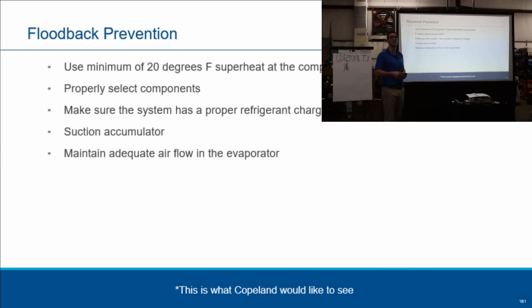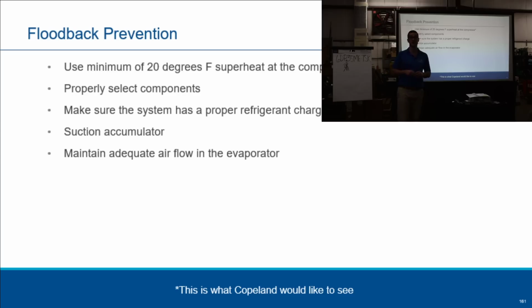It's no different than a supermarket application. I'll get to you, Dick. Supermarket application, you've got a 300-foot pipe run, right? You're probably running at 35 degrees superheat at the compressors. Dick, go ahead. You were talking about the 6 to 8 and 2 to 6 and all that. Was that the evaporator? That's the evaporator, 100%. You never try to adjust your TX valve for your system superheat, like your compressor superheat. 4 to 6 or 6 to 8 and 8 to 12, that's the evaporator superheat. So you should pick up some superheat along the way getting back to the compressor.